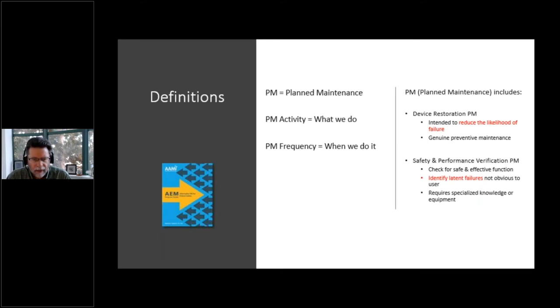CMS and the Joint Commission break that into two things: PM activities, meaning the steps in that procedure, the things that you do, check this output, measure that, leakage current, whatever the activity is. And PM frequency is however you schedule and decide what to do. Typically we say this is due in October or November. But in Joint Commission jargon, that means any kind of scheduling. If you're talking about ventilators and you do those after a certain amount of runtime, that's PM frequency, even though it could be irregular by the calendar.